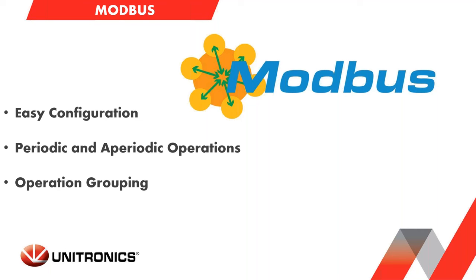Modbus is one of the most common protocols being used today. It's an industry standard and can be communicated both via RTU and TCP networks. Created with a client-server dynamic, the client sends both data and requests to the connected servers. The Unistream can act as both the client and server, and communication is easily configured in the project. Rather than programmed, we have simple periodic operations to read and write data to and from the devices, as well as aperiodic commands, which can be triggered via ladder conditions.